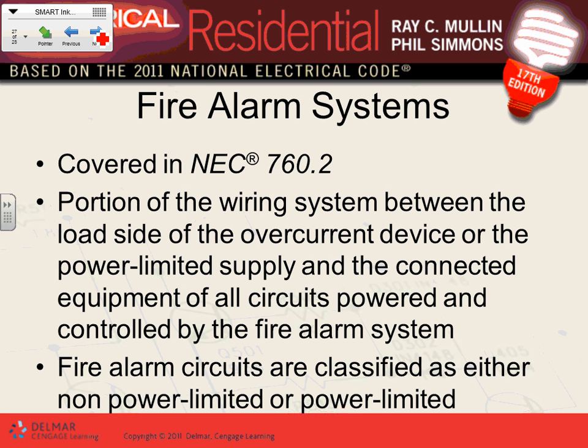Now going, guys, into this article in the NEC code book. The NEC code book takes the fire alarm system and divides it into two systems. Jeff, there is power limited fire alarm system and non-power limited fire alarm system. Most of the systems are called power limited fire alarm system. They run at 24 volt. They're power limited, so people can work on them. The non-power limited fire alarm system, they can work up to 600 volt, and the amount of juice in it is unlimited. Okay, so most of the time you're going to go 760 talks about power limited fire alarm system.